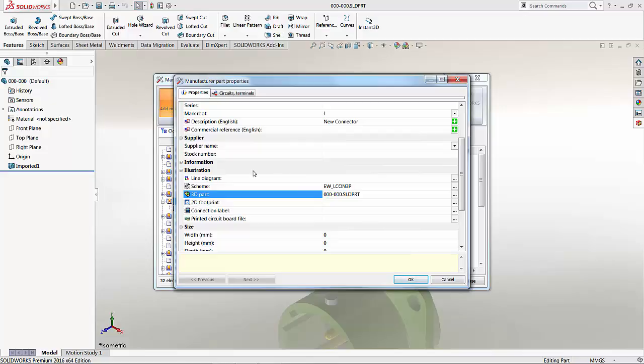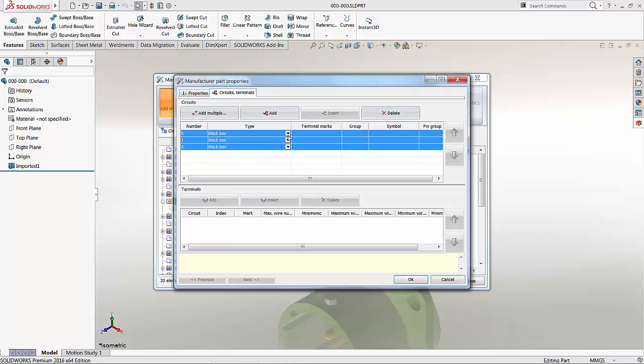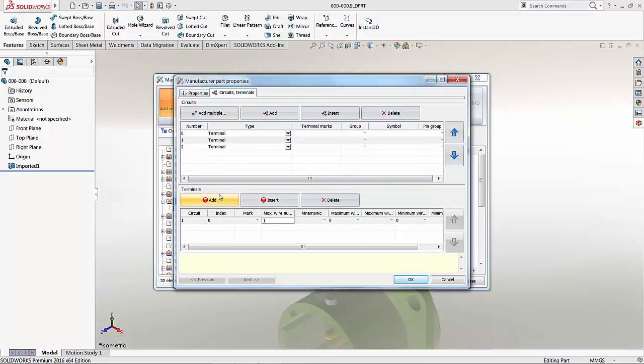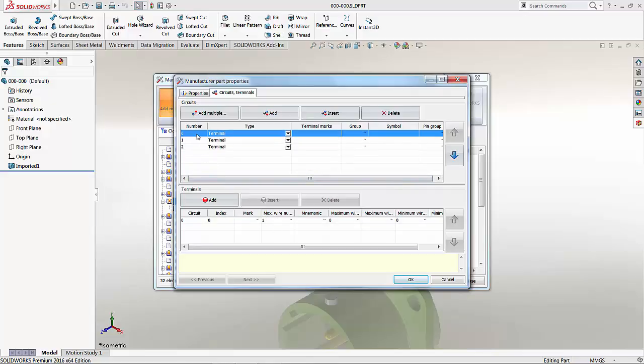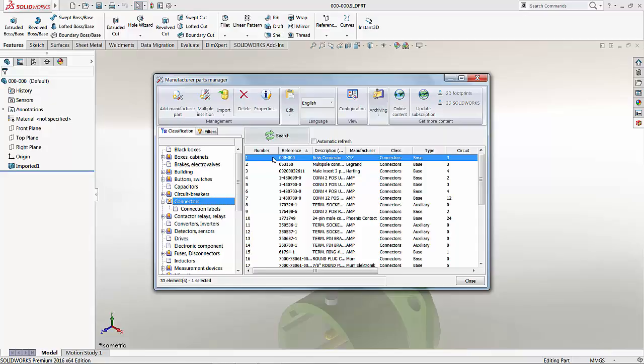So what I've defined here are the basic manufacturing properties. To further add to the electrical intelligence, I'll need to add information defining how the connections to the wires or other components would be. For this new component, I'm going to add three terminals, and I'll change the definition to 'terminal.' In each of these terminals, I'll add the number of wires available for use — for each terminal, one wire. We've now added the circuits and terminal information, defining the basic electrical information for a new manufacturer part inside the manufacturer parts library using the Manufacturer Parts Manager.